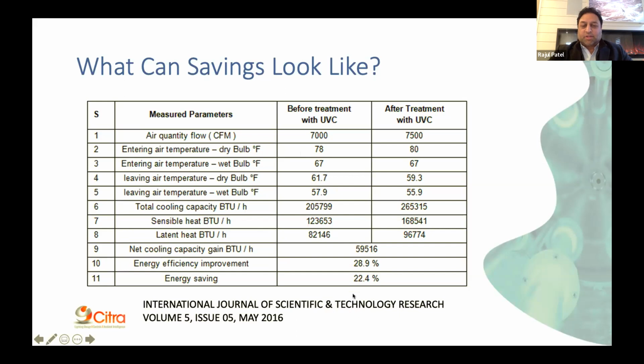This was a study done strictly on the energy savings ability of UV light. Here you'll see before UVC and after UVC, what it does to the air volume, your dry and wet bulb temps, entering and leaving. You'll see leaving wet bulb was at 57.9, now it's 55.9. So they've calculated the net cooling capacity gains here, and what that means from an energy savings perspective.